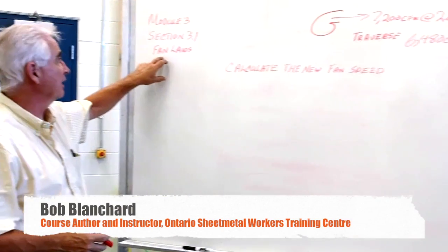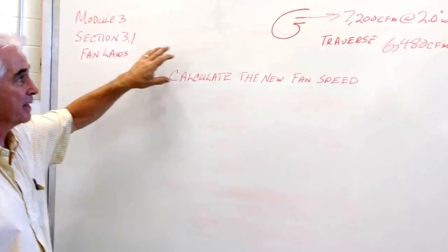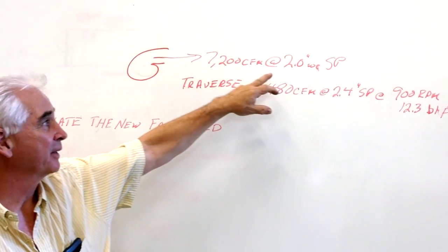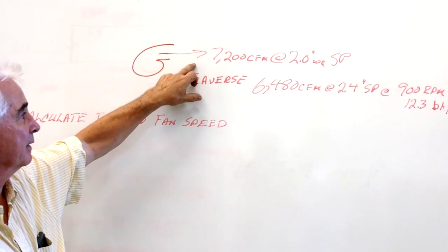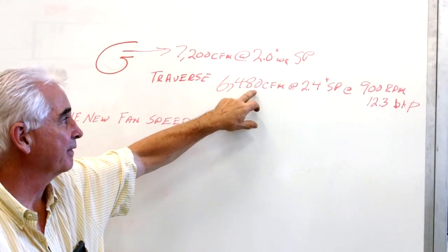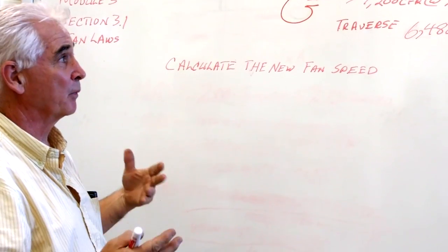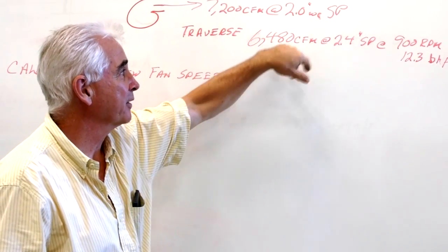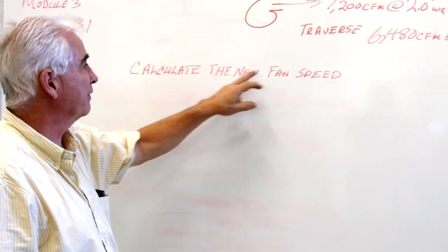This is an example of the fan laws from Module 3, Section 1. The question says the designer wants 7,200 CFM out of the system, designed to work at 2 inches of water column. The technician took a traverse and found there's only 6,480 CFM, but measured the static at 2.4. So the system is more restrictive than the designer calculated — the static is higher, airflow is less. The fan turns at 900 RPM. Calculate the new fan speed.